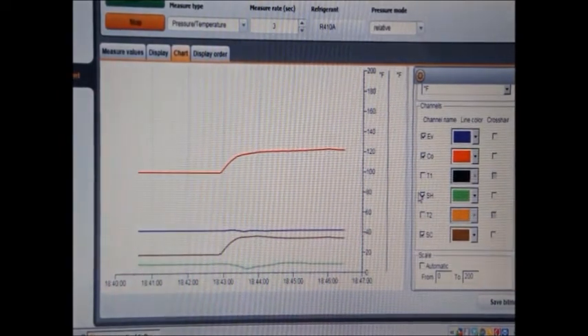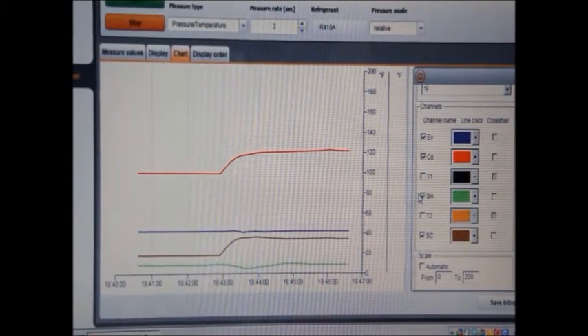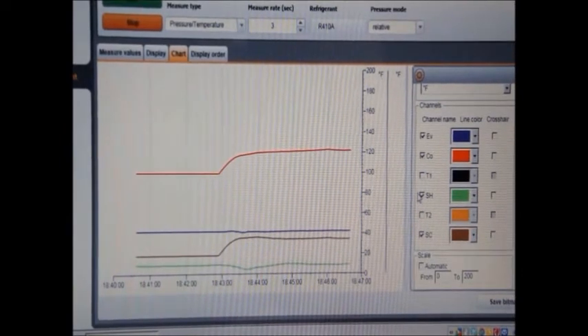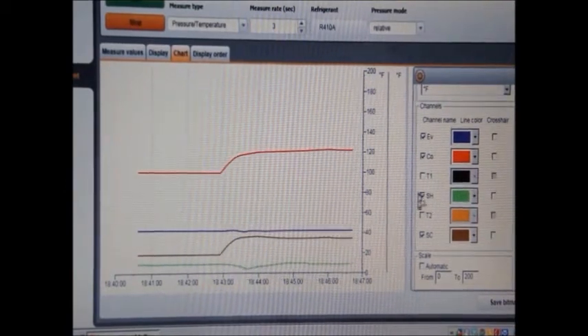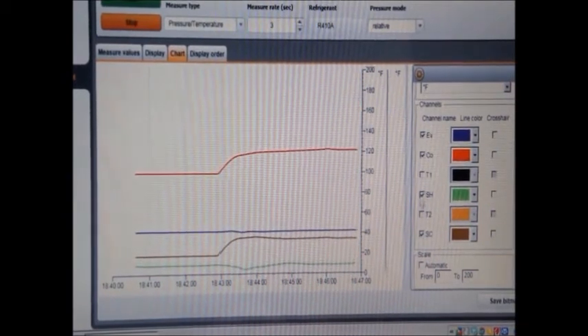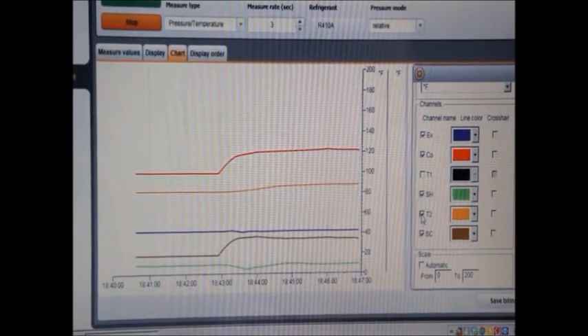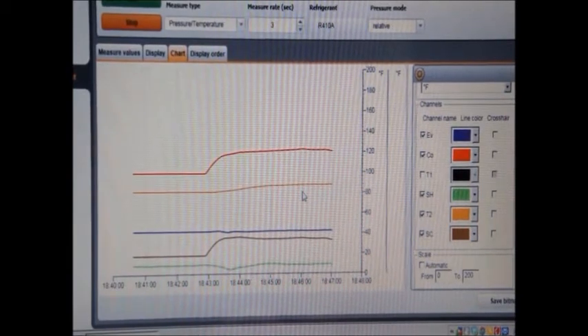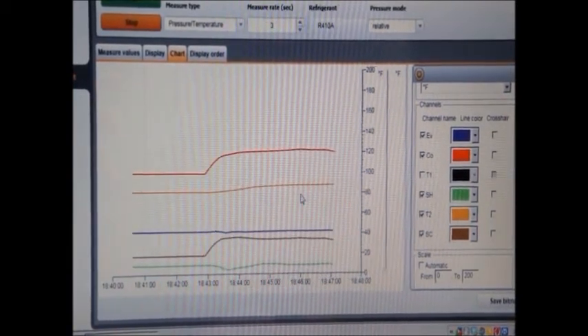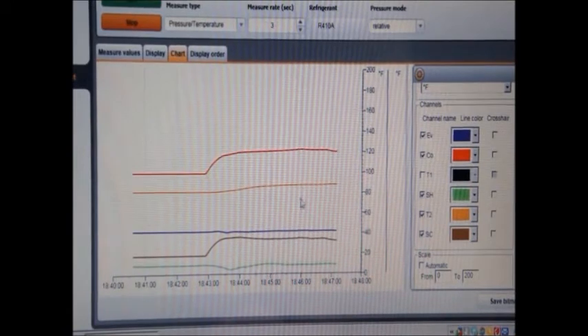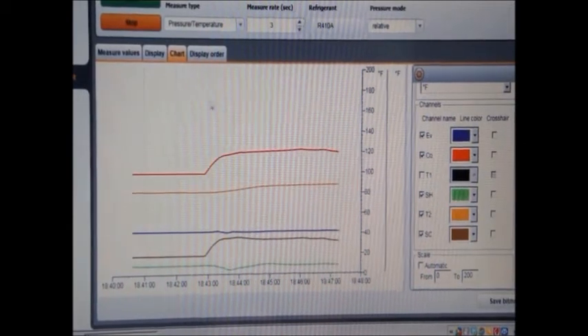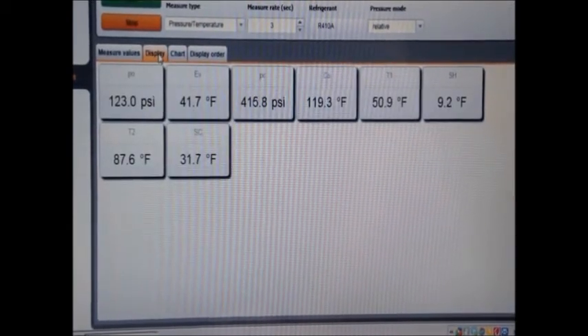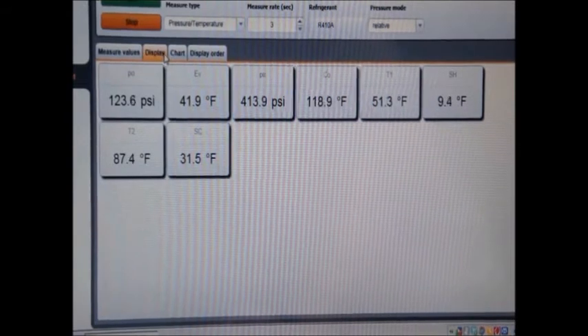This is interesting because basically what we're seeing here is the effect of an oversized condenser. That subcooling is actually showing an increase because we have a higher saturation temperature, higher condensing temperature, but our liquid really couldn't get any cooler than it's running. Let me take a look at T2, which is the orange line. You can see there, even though I blocked the condenser off, there's only a really small change in liquid temperature because the condenser, even though it's plugged with dirt, even though it's 80 degrees or so out here right now, the condenser is so oversized on these newer units it's really not changing it much. If you look closely at that brown line, you can see it is trending down a little bit, but that's about all you can say.